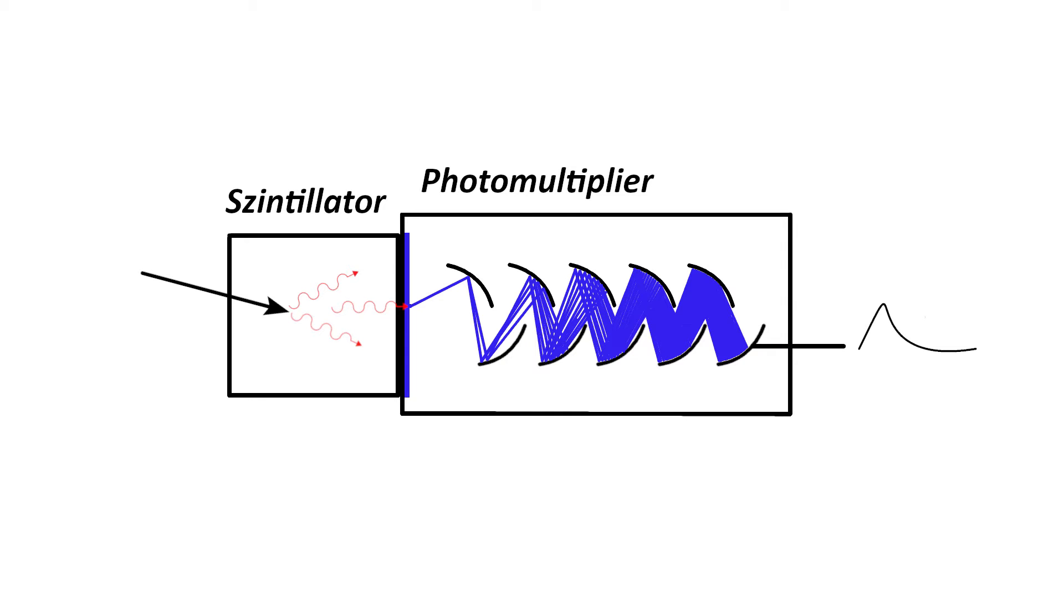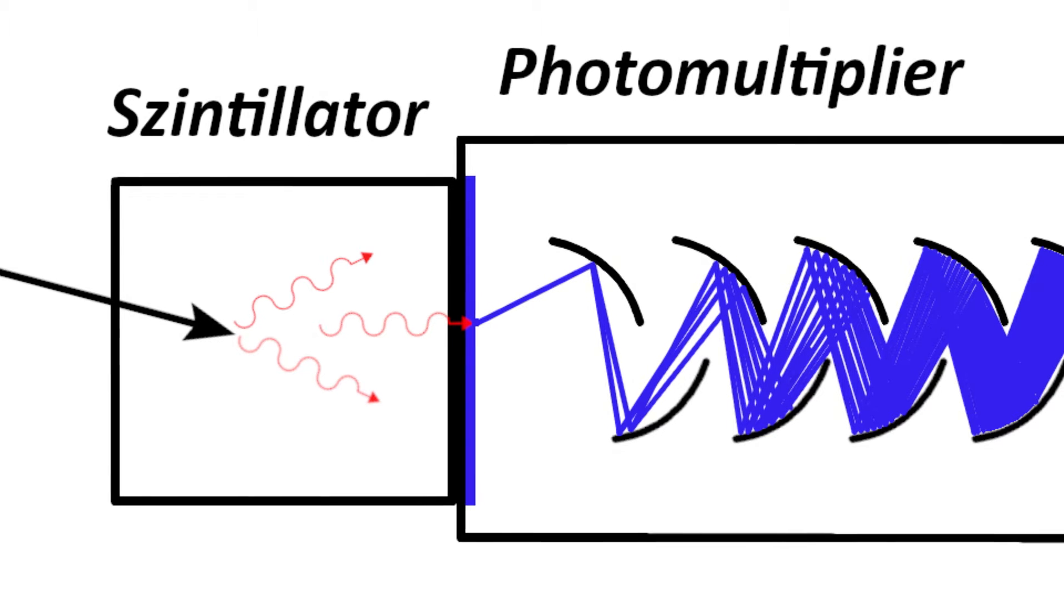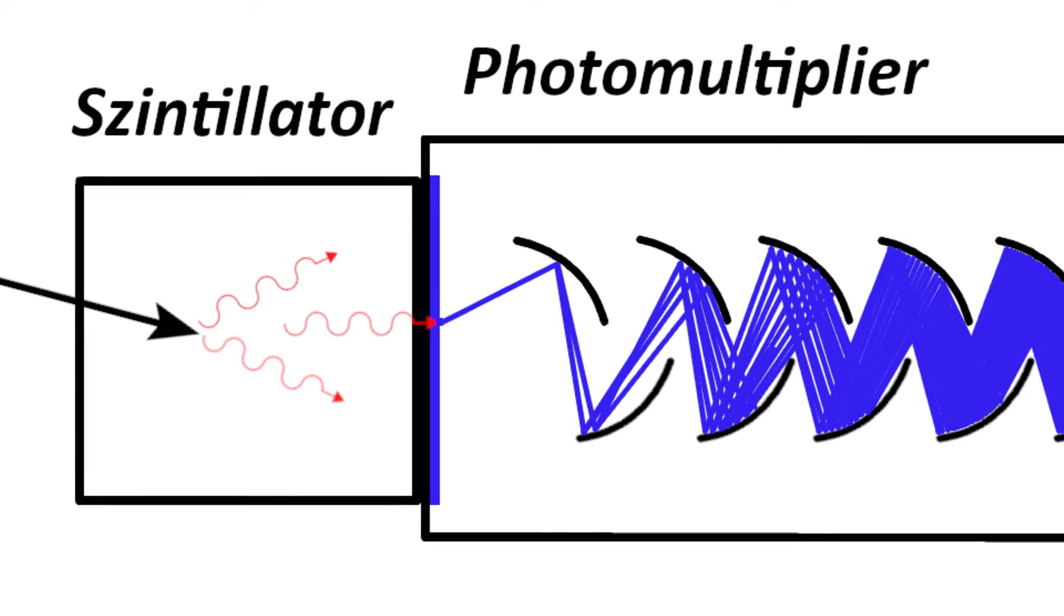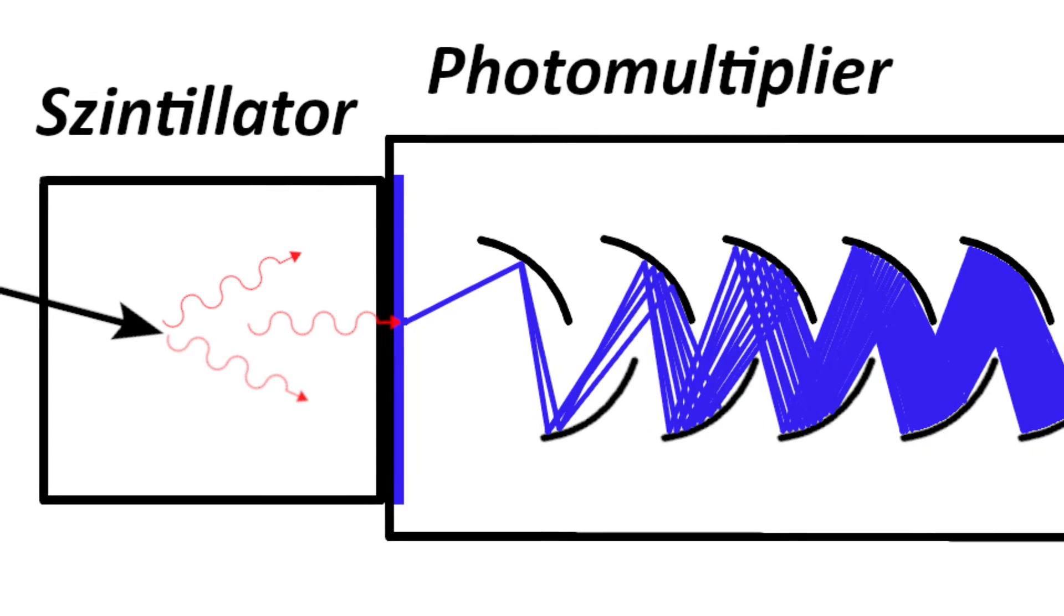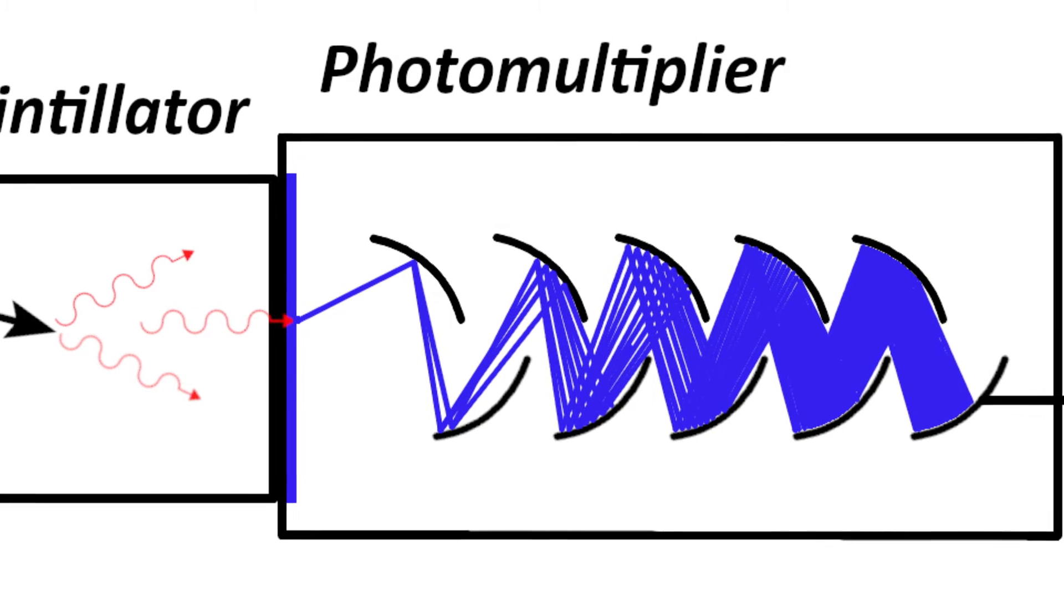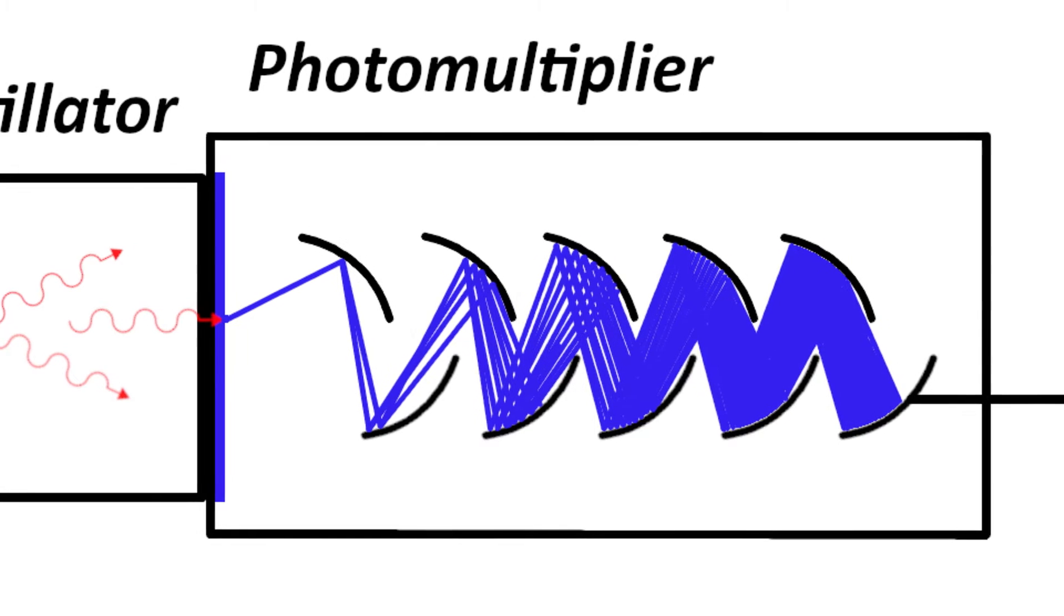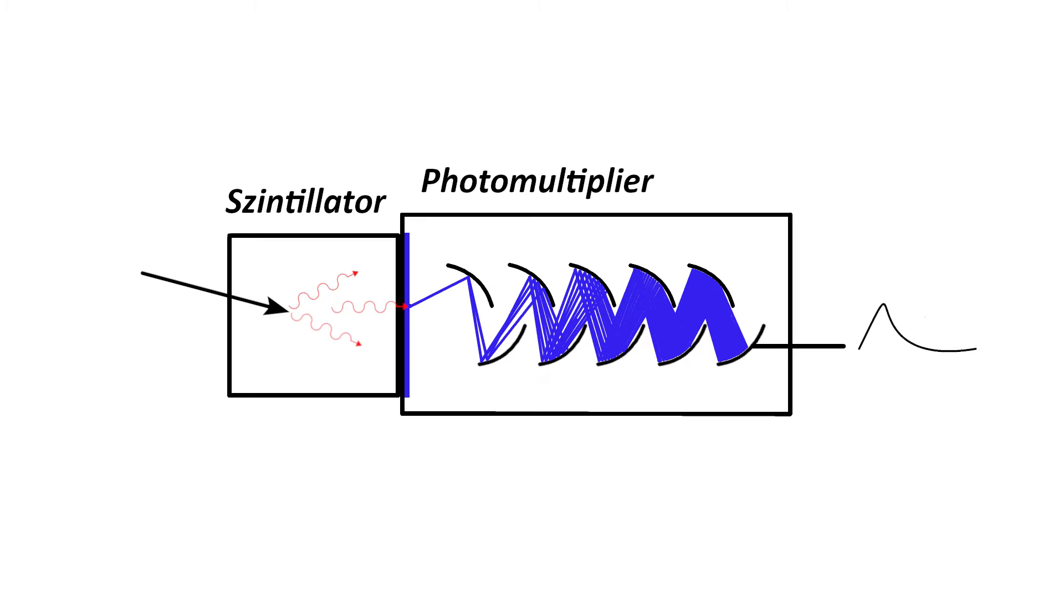Usually instead of a photodiode a so-called photomultiplier tube and a scintillator is used. When radiation hits the scintillator crystal, it converts it into light. This light is super weak and contains only a few photons. These photons get captured by the photomultiplier tube which converts it into an electrical signal and amplifies it.